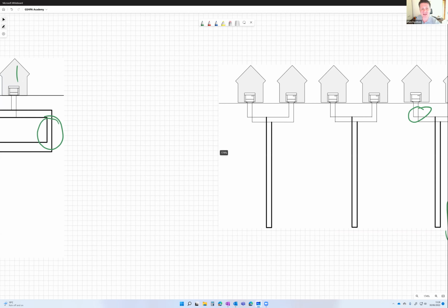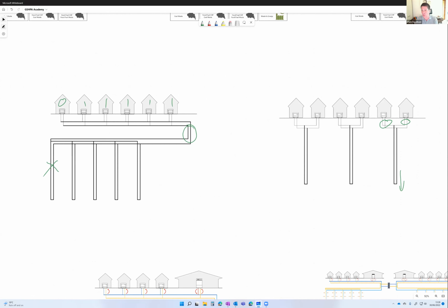So our design is a balance between connecting all together and getting maximum diversity, or distributing it. The other reason you might want to connect it all together is, for example, if we've got a solar farm connected to this ground loop. You'd want that heat from the solar thermal to be transported around your whole network. That might be a solar farm, or any other waste heat from sewage, whatever. That would drive you towards a connected heat network.